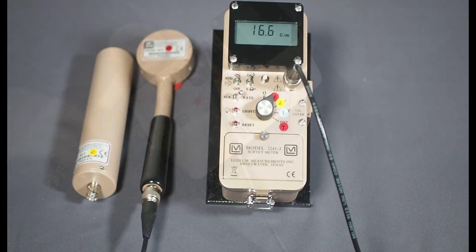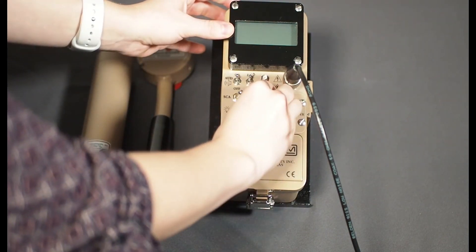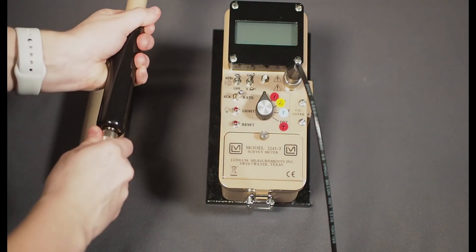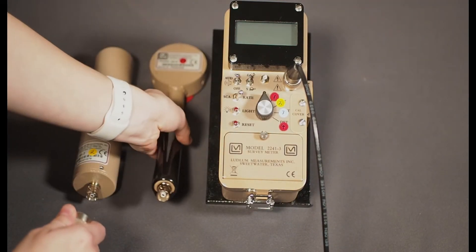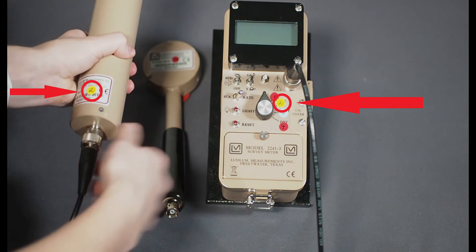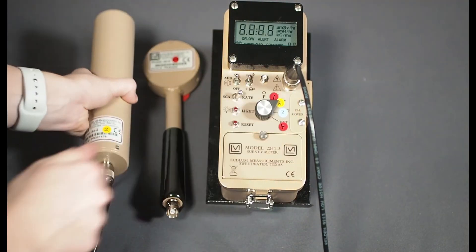Be sure to turn off the meter before changing detectors to avoid damaging either the detector or the 2241. In this example, we are disconnecting the 44-9 and connecting the 44-2 detector. Connect the model 44-2. Match the colored dots on the detector to the colored dot on the meter. Turn the rotary switch to the detector 2 setting.